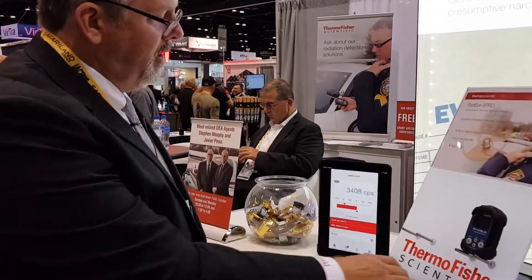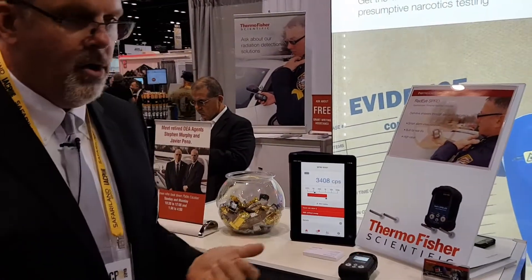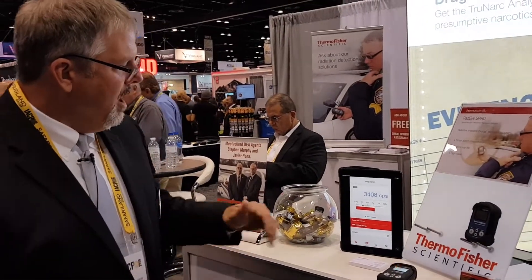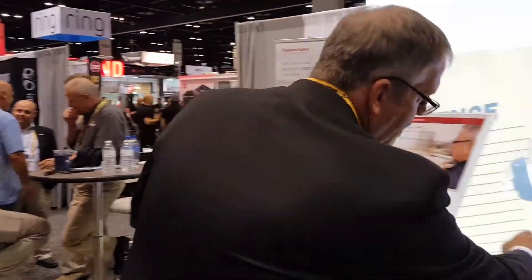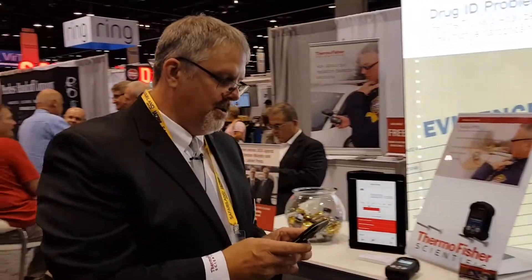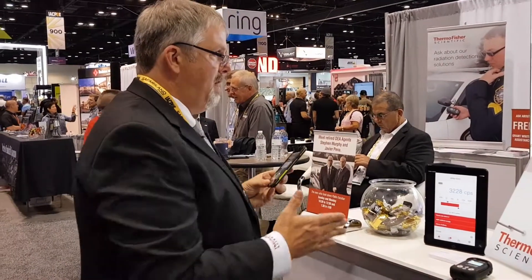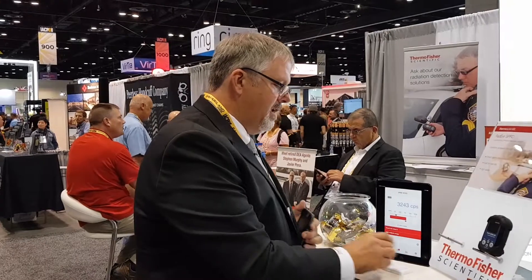I'll have an alarm show up — whether it's on my phone; in this case it's on the tablet. I'll have the counts per second, and I can just like a million other people be looking at my phone. Using the counts per second, I can slowly pivot and try to determine the location where the radiation is coming from, and that will help me adjudicate and try to find it or at least narrow it down.